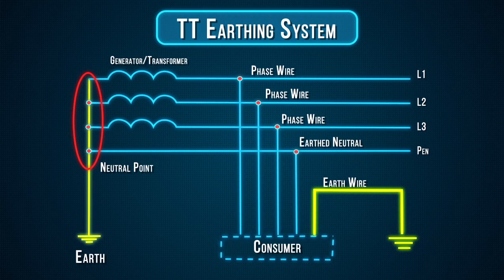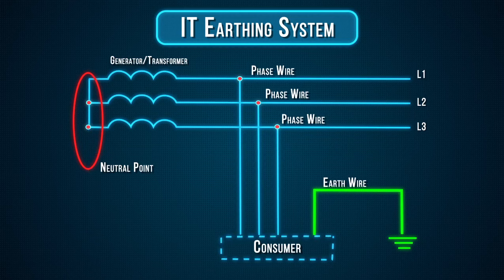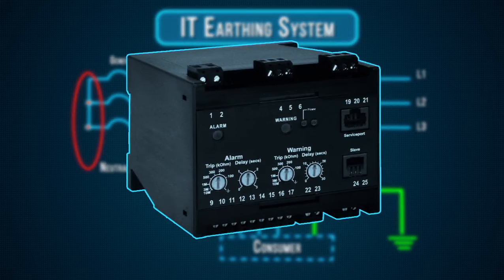In an IT network, the electrical distribution system has no connection to earth at all, or it has only a high impedance connection. In such systems, an insulation monitoring device is used to monitor the impedance.